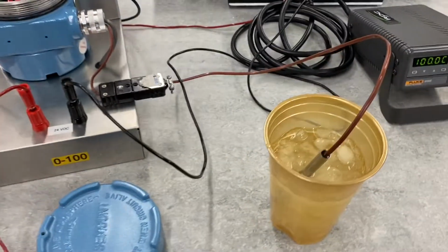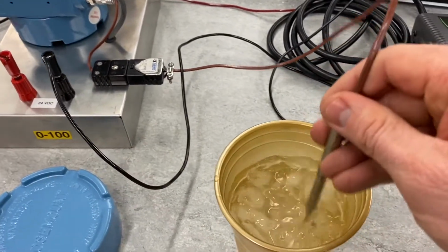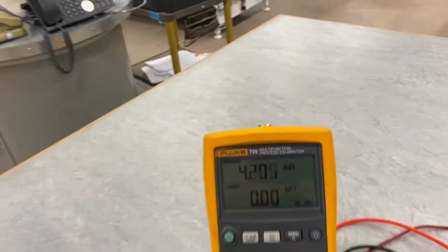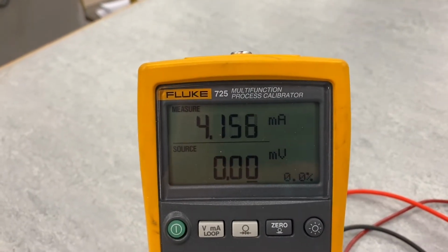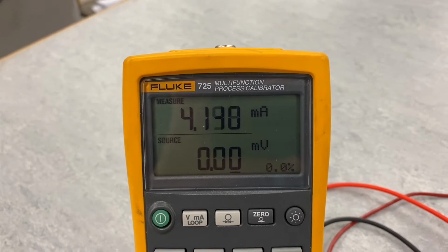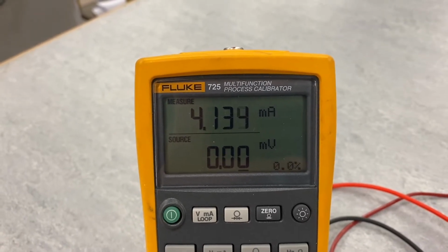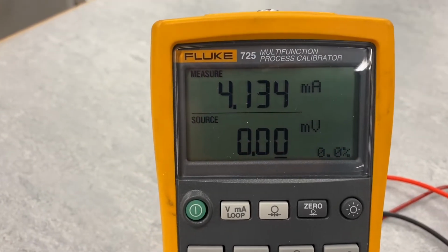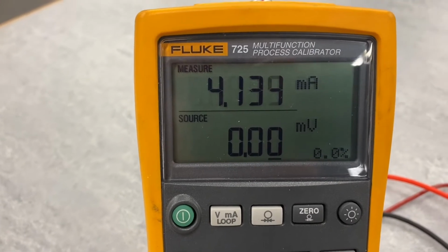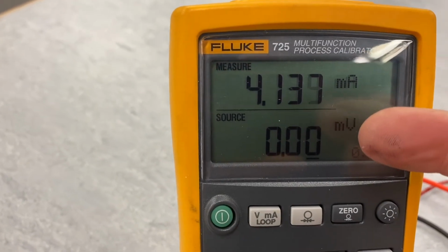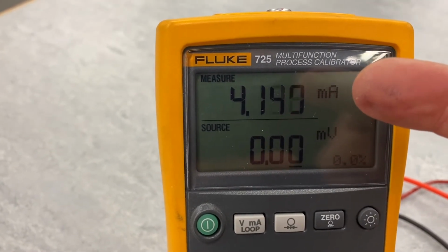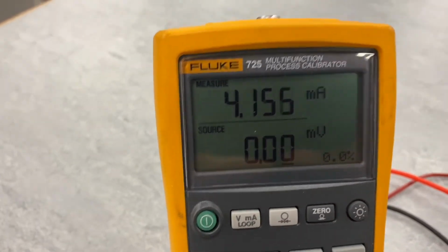What we need to do when we're doing this calibration is make sure that we're agitating the ice bath here, because you can already see our milliamp value is dropping. So you want to keep that agitated as we're doing the calibration. The first step here is we're going to be sourcing 0 millivolts. You can see on the bottom side here we're sourcing 0 millivolts. Up here we're measuring the 4 to 20 milliamp signal, the current signal output of the transmitter.